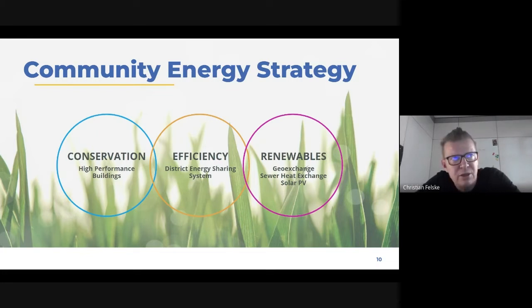Renewables form the third pillar, provided initially through a geo-exchange field, which I'll show some pictures and slides of in a second. It's the ability to get heat from the ground in the winter when we need it, but also put heat back into the ground in the summer, when the system runs more like a cooling loop. It's a tremendous opportunity to use the heat and energy stored in the ground for heating and cooling purposes all year long.